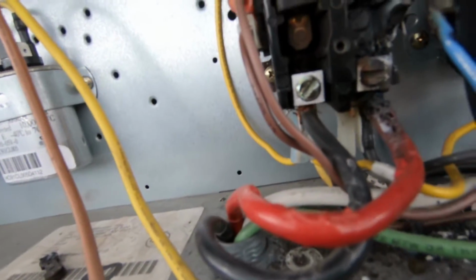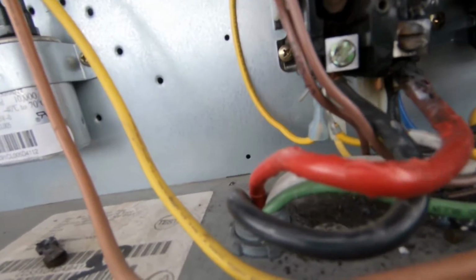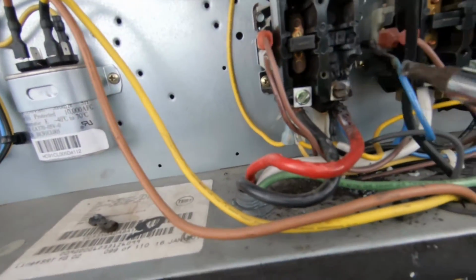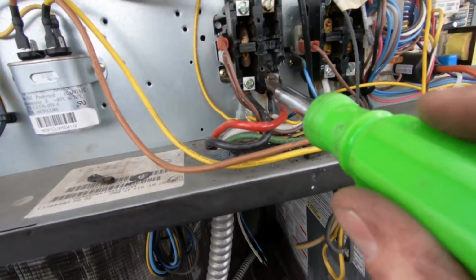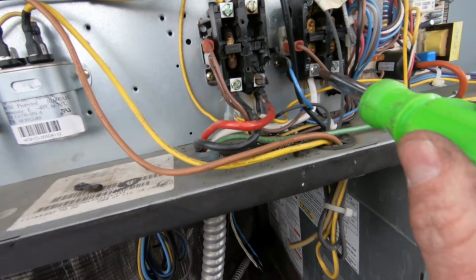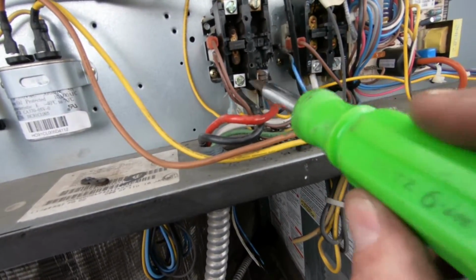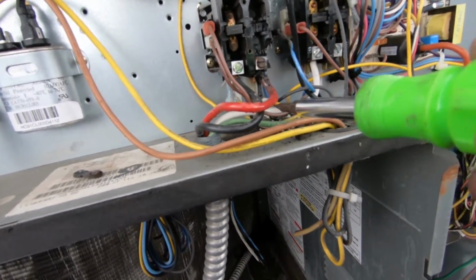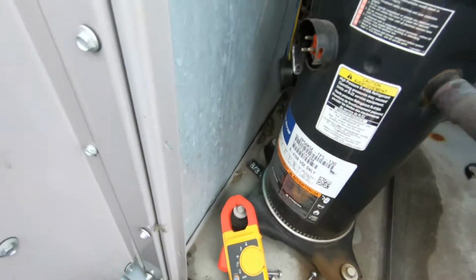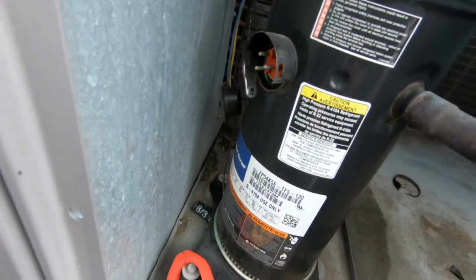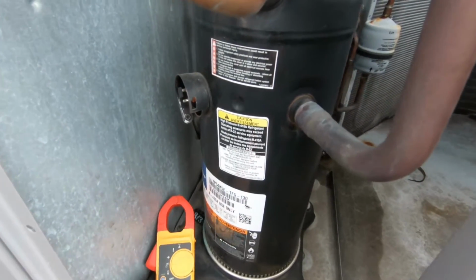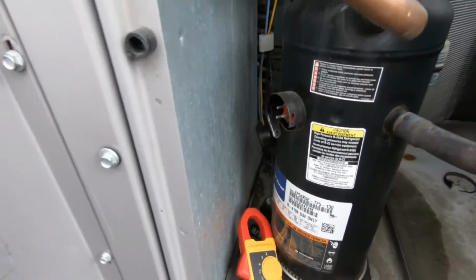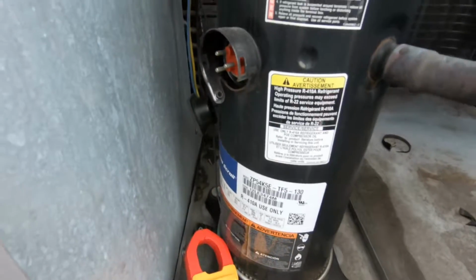So I'm gonna be leaving the power off to this unit, considering these two contactors, 208, 3 phase, you land the power on these two contactors, 2 legs here and 1 leg here. So, all right, well, I think I found the issue as to why those wires were all burnt up and that contactor is toast.